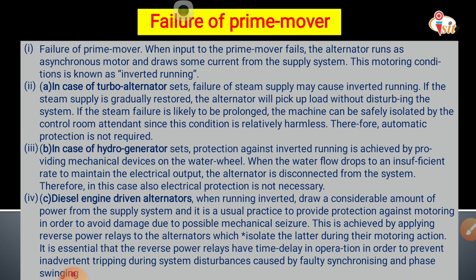For a hydro generator, protection against inverted running is achieved by providing a mechanical device on the water wheel. When the water flow drops to an insufficient rate to maintain the electrical output, the alternator is disconnected from the system. In this case also, electrical protection is not necessary.